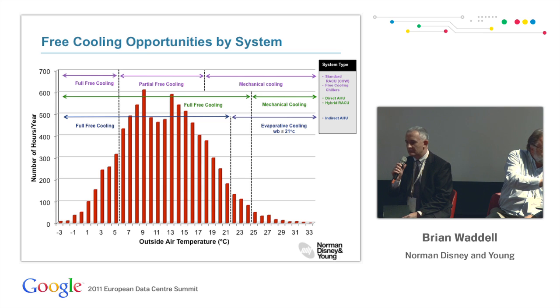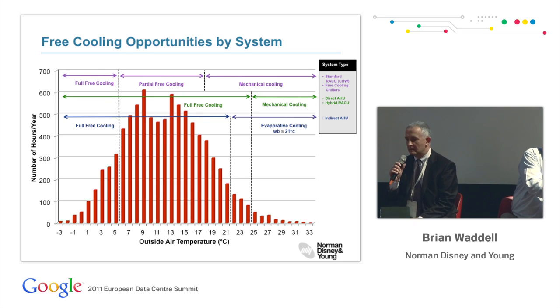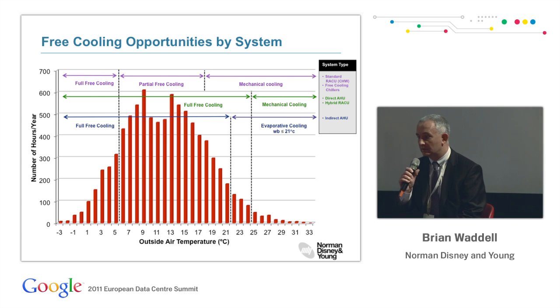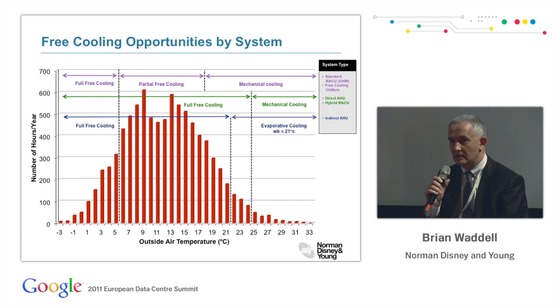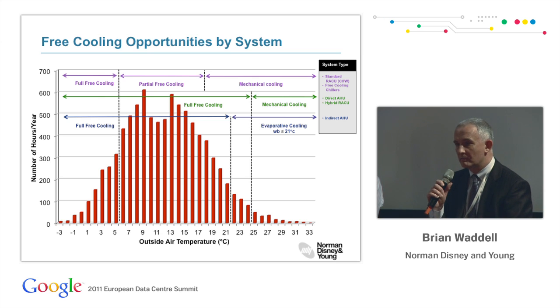This slide demonstrates the temperatures in and around London across the year—how many hours at a particular temperature. From that you can see there's an opportunity to use free air cooling. The three bars across the top show three different ways that can be done. One way is with free cooling chillers, giving a fairly short period of total free cooling, a reasonably long period of partial free cooling, and then mechanical cooling on top of that.